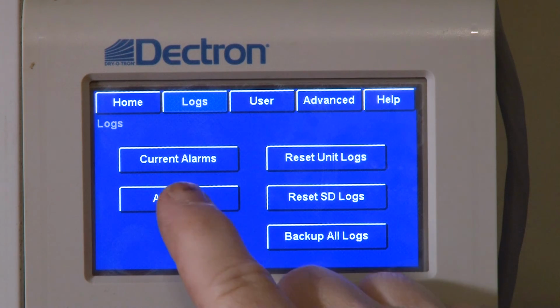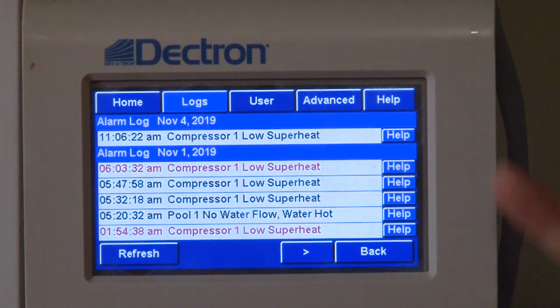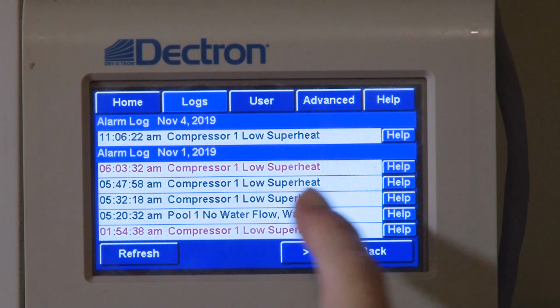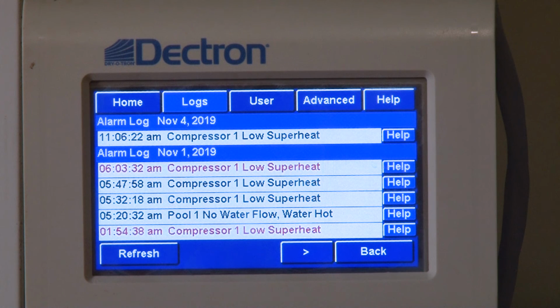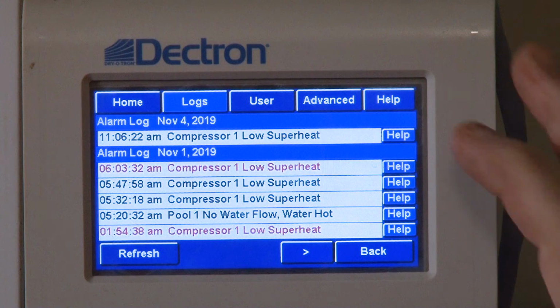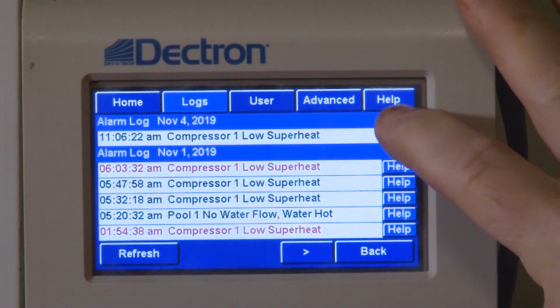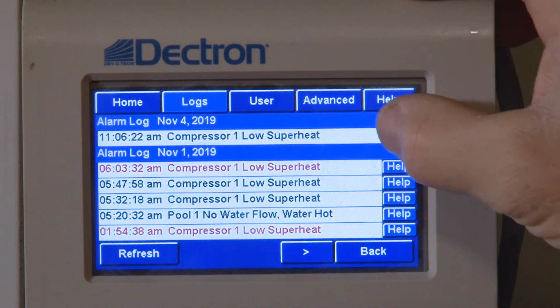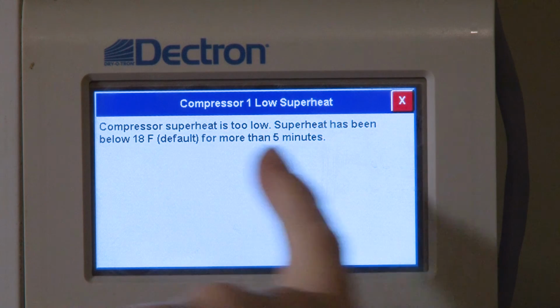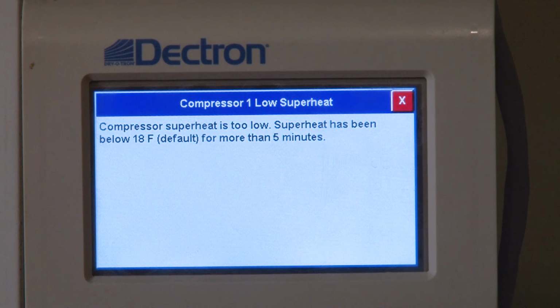You can also go into the alarm log, and that's going to give you a record of all of the alarms that have been recorded in the unit. It's going to give you the date and the time that the alarm happened, and also a brief description. If you want to get an explanation of what that alarm message might be, you can press the Help button, and it's going to give you a description of what that error actually was.